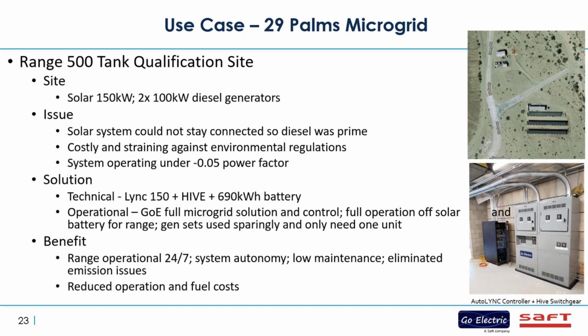This system has been operating autonomously now for almost a year after our solution was commissioned. The generators have run a couple of times, basically to help build up the battery, not to manage the operation. So the generators are now there to bring the battery up to a proper state of charge, because the solar system wasn't able to manage that on its own. So your runtime is reduced dramatically on those generators.